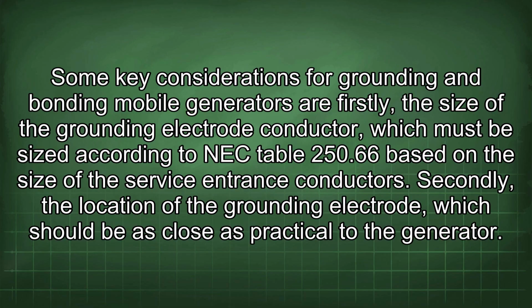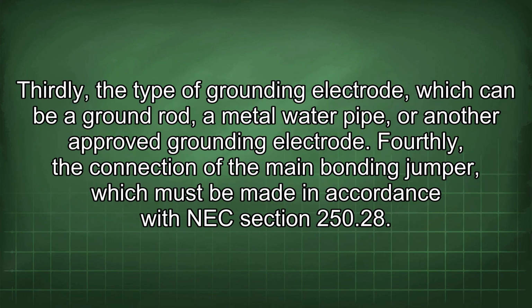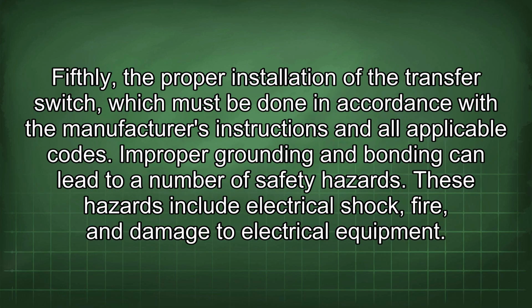Some key considerations for grounding and bonding mobile generators are: firstly, the size of the grounding electrode conductor, which must be sized according to NEC Table 250.66 based on the size of the service entrance conductors. Secondly, the location of the grounding electrode, which should be as close as practical to the generator. Thirdly, the type of grounding electrode, which can be a ground rod, a metal water pipe, or another approved grounding electrode. Fourthly, the connection of the main bonding jumper, which must be made in accordance with NEC Section 250.28. Fifthly, the proper installation of the transfer switch, which must be done in accordance with the manufacturer's instructions and all applicable codes.